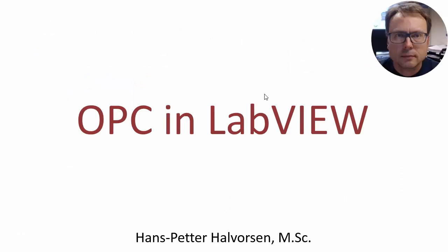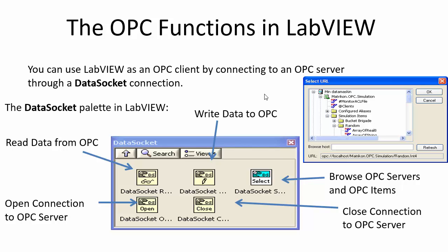Next, how do we use OPC in LabVIEW? In order to use OPC in LabVIEW, we need to use the data socket palette. We have the data socket write, which we use to write to the OPC server, and we have the data socket read, which we use to read values from the OPC server. We also need to open a connection to the OPC server where we start to read or write, and then when we are finished, we need to close the connection.